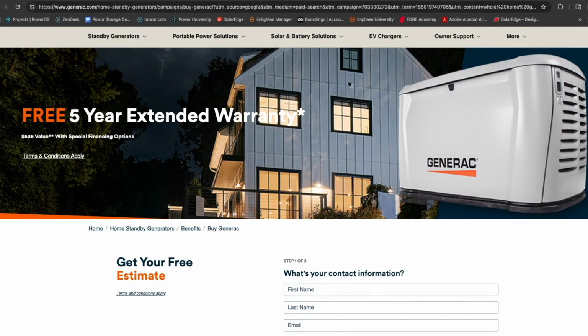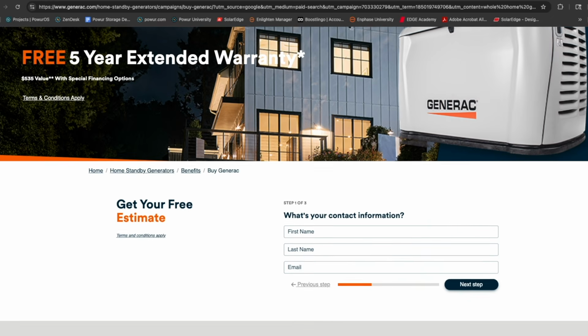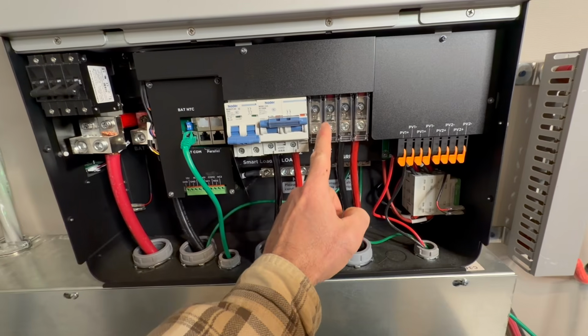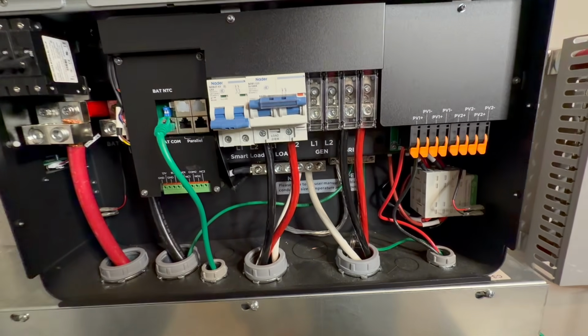So with this inverter, you have two options for standby generator integration. One, if you've got a large whole-home style generator that produces nice clean power, you can tie that directly into the generator inputs built into the system itself. For those of you that might have a cheap portable standby generator with dirty power - most do if you're under that $1,000 threshold - you generally don't want to tie that directly into your home with sensitive electronics or large loads.